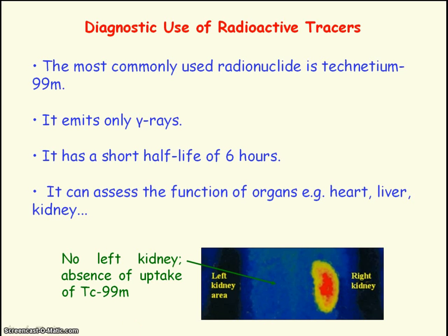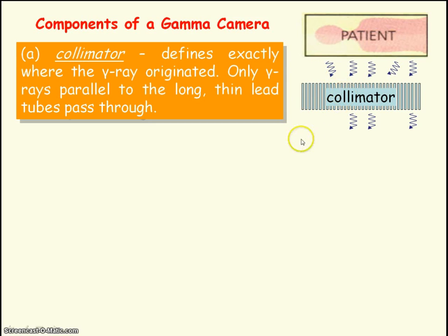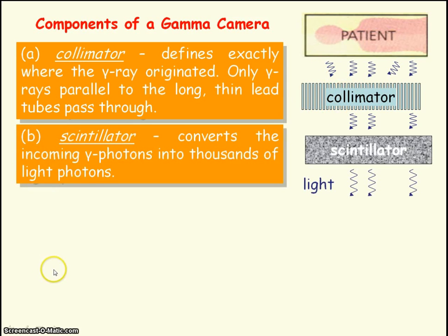This is showing that the patient has no left kidney. The gamma camera detects the gamma radiation penetrating out of the patient and has four main components. The first component is the collimator, which defines exactly where the gamma rays came from inside the body. The collimator is made up of long thin parallel lead tubes, and only gamma rays parallel to these tubes can pass through — any gamma rays meeting the lead tubes at an angle will be absorbed.